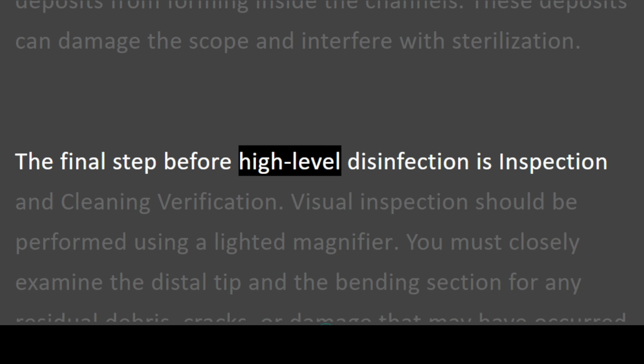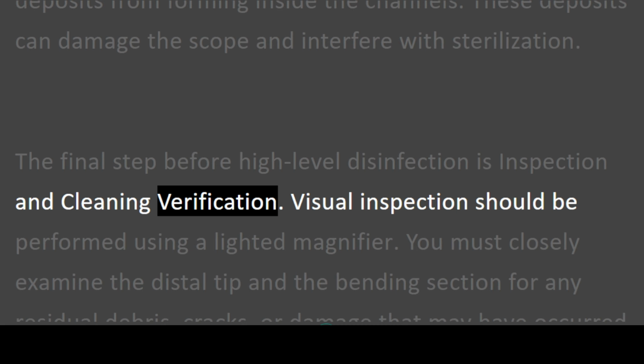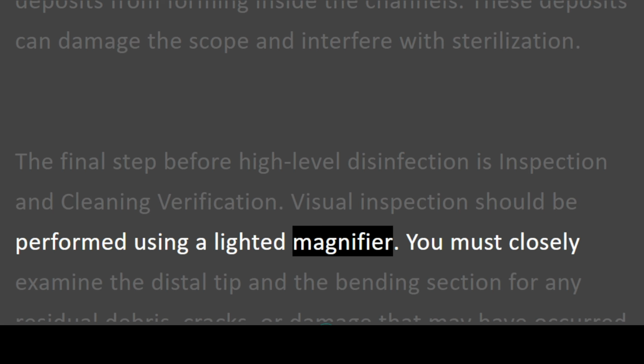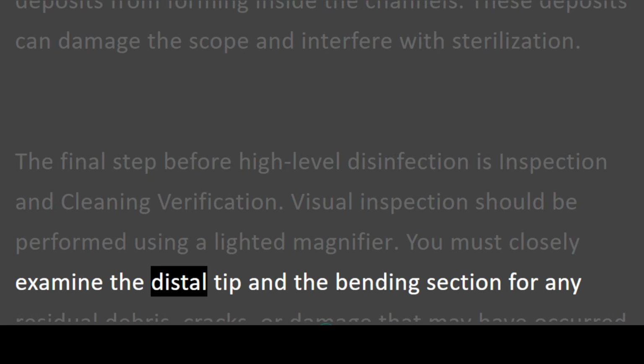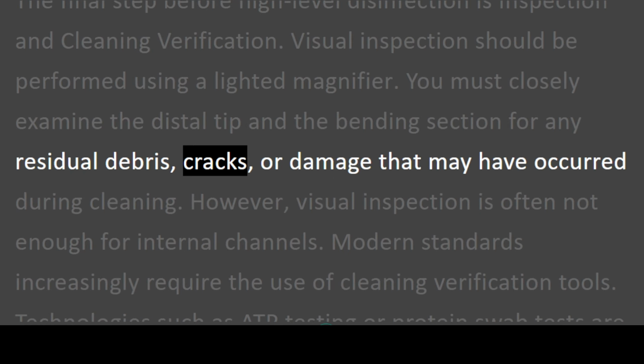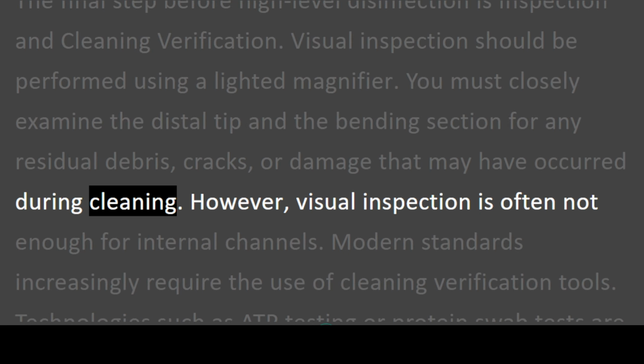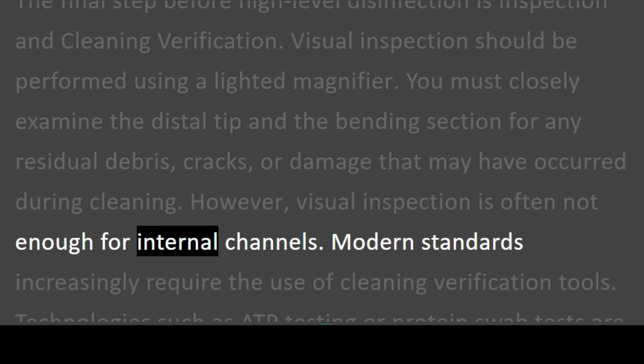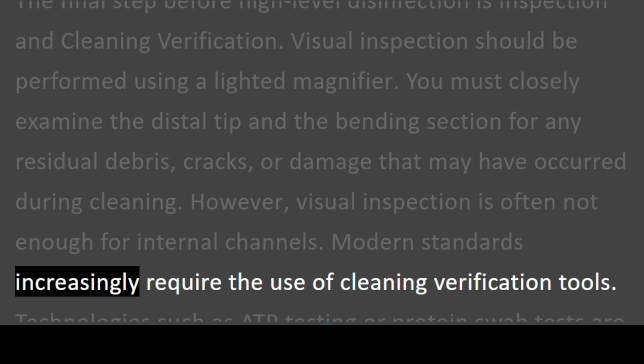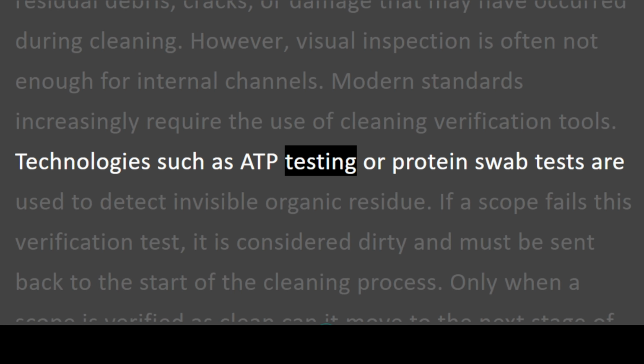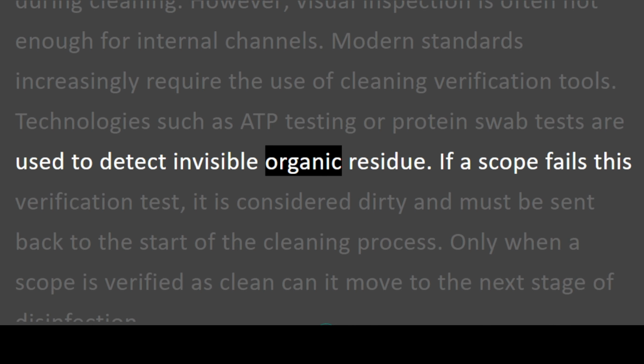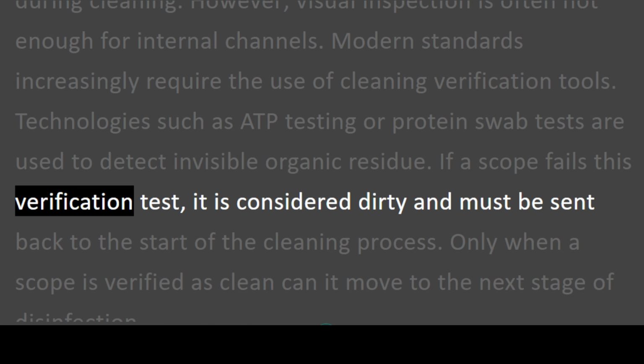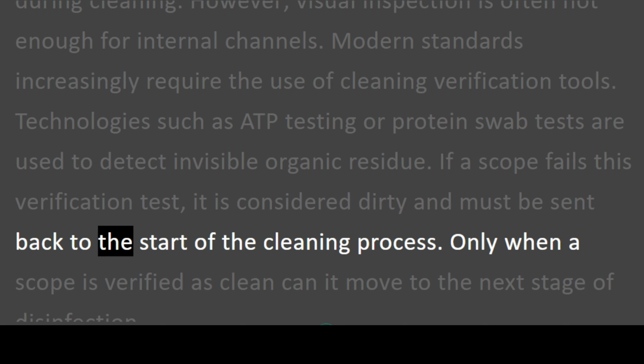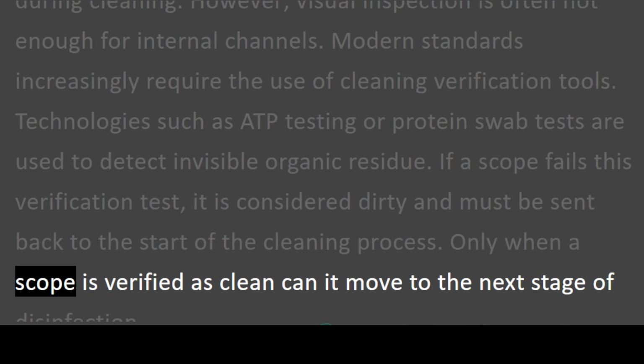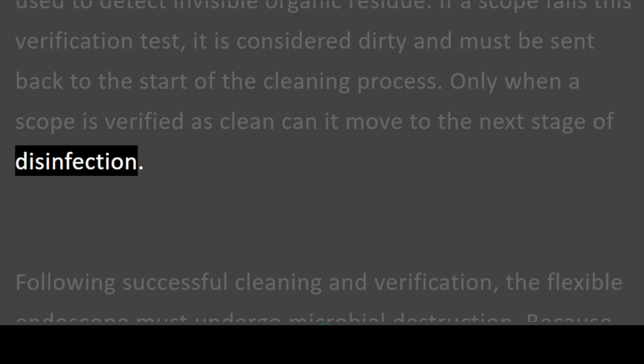The final step before high-level disinfection is inspection and cleaning verification. Visual inspection should be performed using a lighted magnifier. You must closely examine the distal tip and the bending section for any residual debris, cracks, or damage that may have occurred during cleaning. However, visual inspection is often not enough for internal channels. Modern standards increasingly require the use of cleaning verification tools. Technologies such as ATP testing or protein swab tests are used to detect invisible organic residue. If a scope fails this verification test, it is considered dirty and must be sent back to the start of the cleaning process. Only when a scope is verified as clean can it move to the next stage of disinfection.